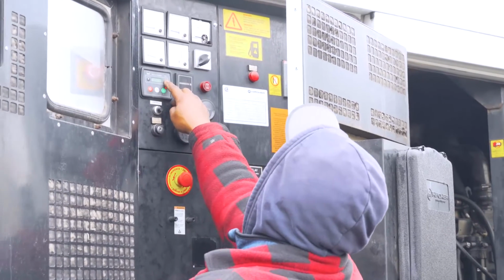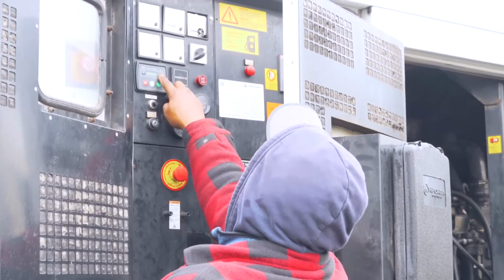So common alarms are generally set within the control panel to control the operation of the generator. And one way to control the operation of the generator is to not start it when certain alarms are on. Some of those alarms might be low fuel. If your fuel is low or it's getting low, again, some generators are set to different ranges, your generator is not going to start. If you have low coolant level, your generator is not going to start. If you have low coolant temperature, most of the time, if you have a common alarm within your generator, that generator is not going to start.